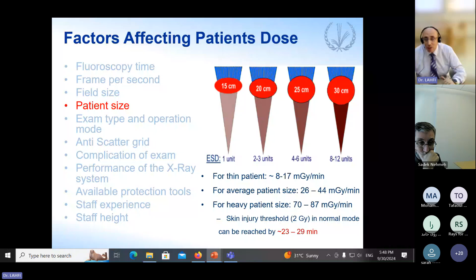Patient size: the doses are related to the patient size. Thin patients receive lower doses than heavy patients, as we can see here. So for a thin patient, 8 milligray per minute, and for a heavy patient, perhaps 10 times more, which may reach 70 milligray per minute. Keep in mind that skin injury may appear after 2 gray in normal mode.